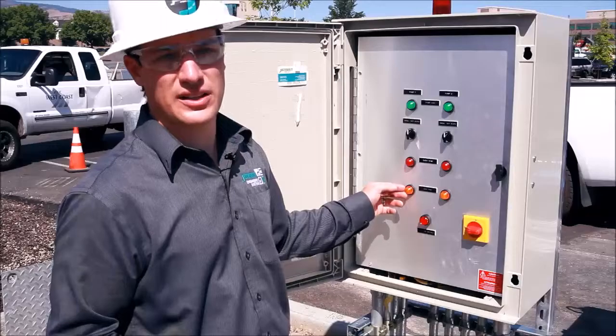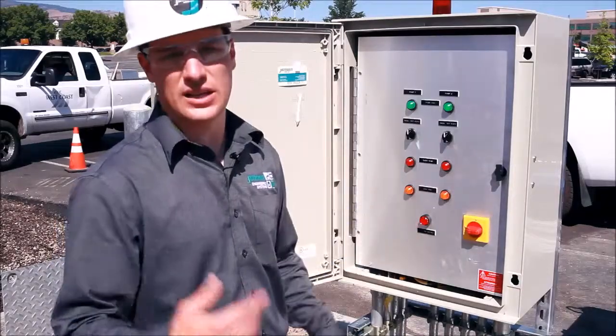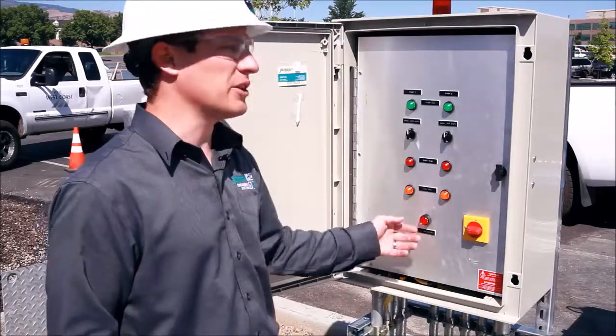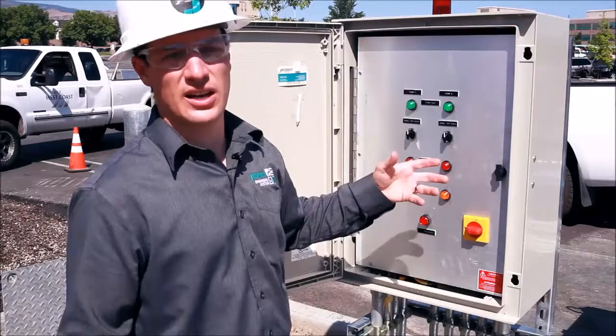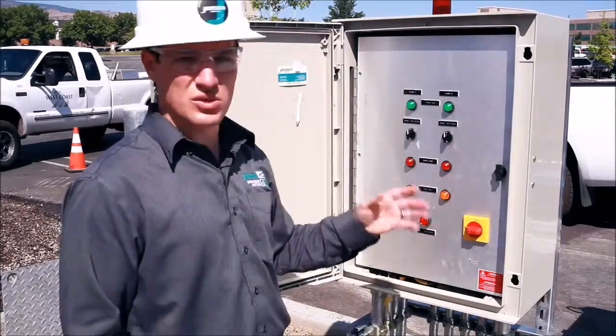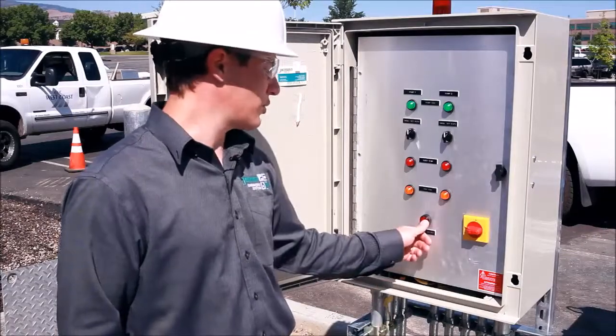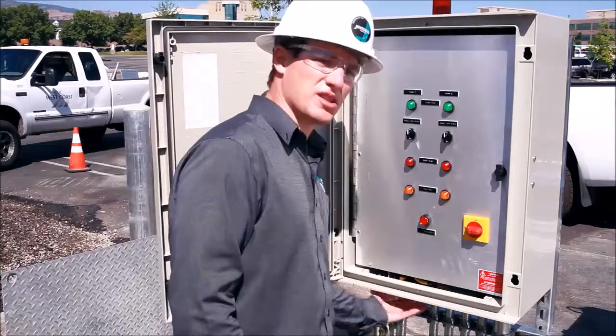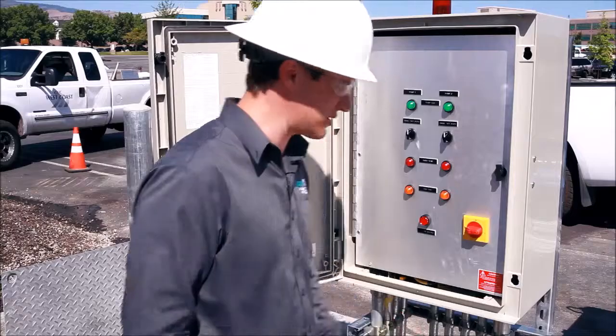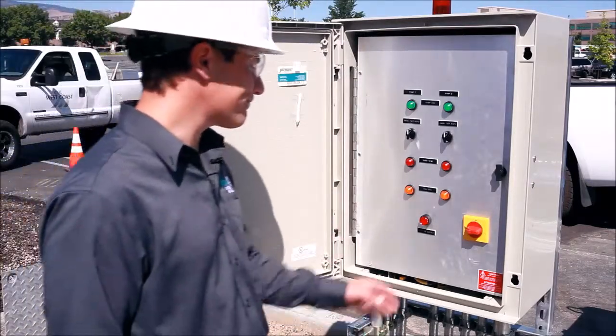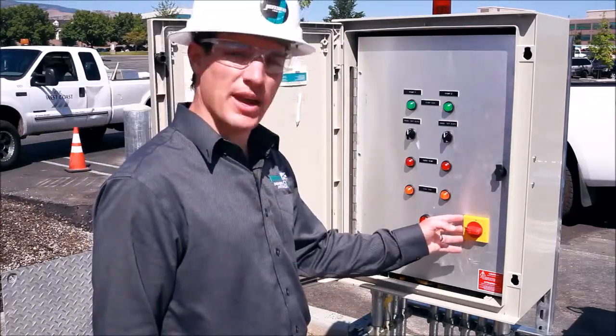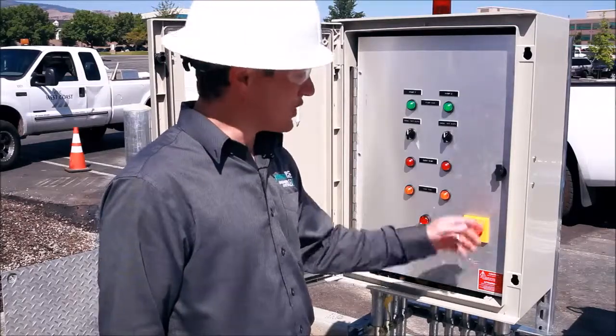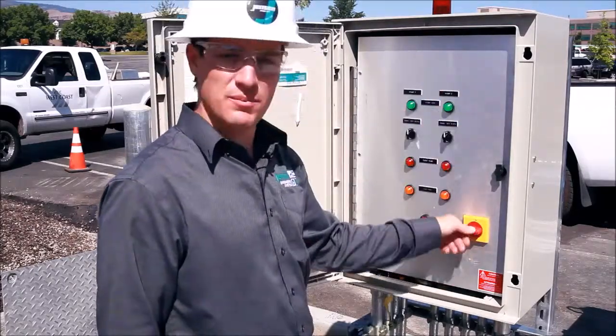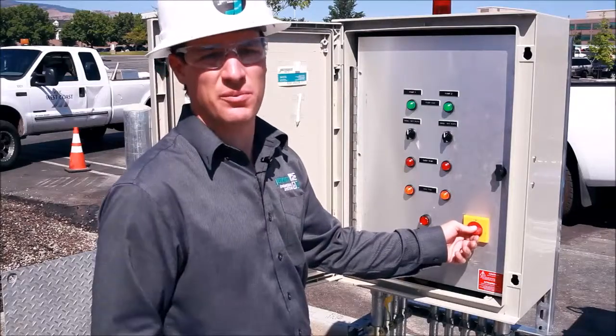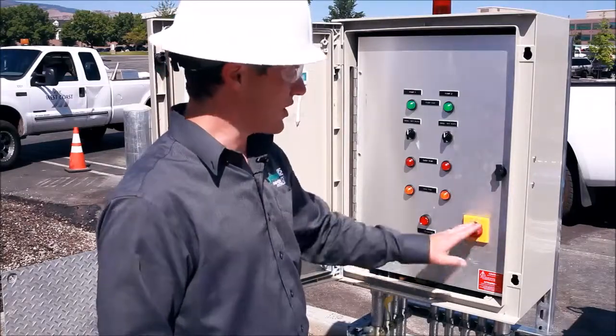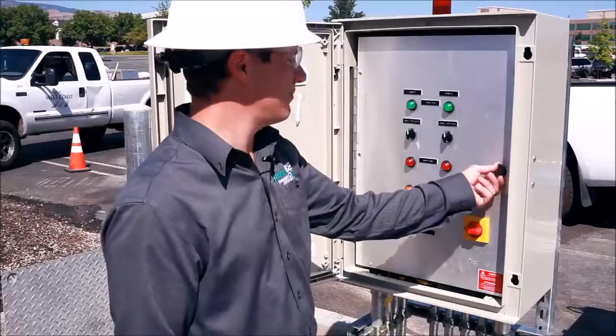This is where the seal fail indicator lights are, so if you see these lights lit up, that's indicating to you that you do have a seal fail. And finally, on any of our alarms, it's going to generate an audible alarm and then a visual alarm. To silence the audible alarm, you can push that button there. There's also another push to silence button on the bottom of the panel that you can depress to silence the alarm. And finally, on the front of the panel, we have our main disconnect. You cannot get behind the dead front until you put the main disconnect in the off position, thereby protecting the operator. So right now we're in the off position, so we can go ahead and enter the panel.